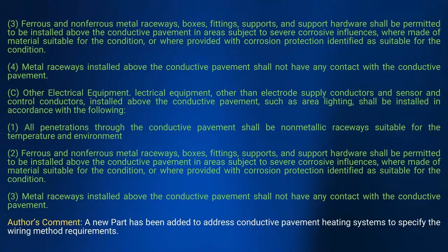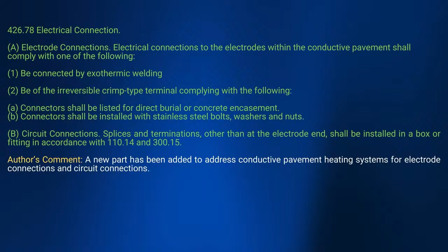Then they get into the electrical connection portion here, and this is where you got your electrode connections. And they're telling you when you make these electrical connections, these electrodes within the conductive pavement system, what is required? It can be connected by exothermic welding. It can be the irreversible crimp type terminal. But if you use that, it's got to comply with these two here. Connector shall be listed for direct burial or concrete encasement, or shall be installed with stainless steel bolts, washers, and nuts. And then you got your circuit connections, and they tell you, your splices and your terminations, other than on the electrode end, shall be installed in a box or fitting in accordance with 110.14 or 300.15. Same rules apply, basically.